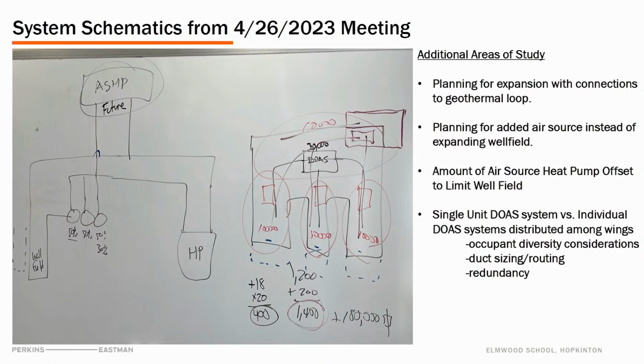That gives us the ability, in a couple of ways. One, it helps me expand in the future, but also helps short term if we have a budget issue, or if thermal conductivity comes back and says we really need 200 wells to make this work today, and we can't afford 30 more wells, then we can go this route in a more economical way. It'll have an EUI impact, but it wouldn't be a huge deal breaker in terms of what we're trying to do. So it gives us the ability to shift as the project develops and the budgets keep coming. That gives us a little bit of flexibility.